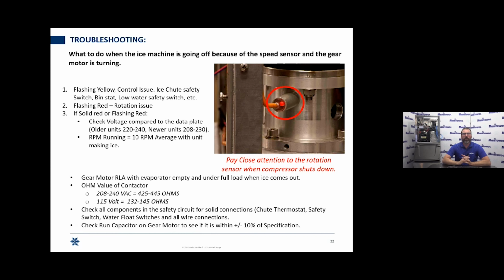So just a couple of pointers here. If we come up to a machine, because of the speed sensor, the gear motor is turning, but it's still flashing red, something's going on here. Like I talked about earlier, we're going to want to see what exact LED condition we have. Of course, if it's flashing yellow, we're in a time delay period, we're just in a startup. That's to be expected. We can always bypass this if we look again for those 2 black wires going into that connector. That is a bypass.